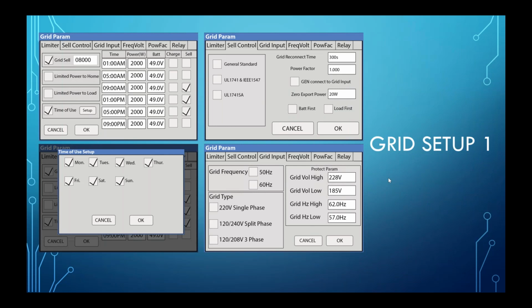And then moving on, the Sell Control tab and the grid parameters tab, those are really important if you're trying to select your 120/240 or 208 3-phase, 50/60 hertz. You have your grid hertz high, your grid hertz low. Those are typically pre-selected by UL 1741 SA, but you can adjust those if you select general standard. Those are what we typically use for off-grid. So very customizable in the sense of whatever project you're trying to do. If you ever have any questions, or if you're ever curious what mode works best, or especially for generator connections, we can widen the frequencies to be a little bit more forgiving. Just give us a call and we can point you in the right direction and help you get it set appropriately for what settings you're needing.